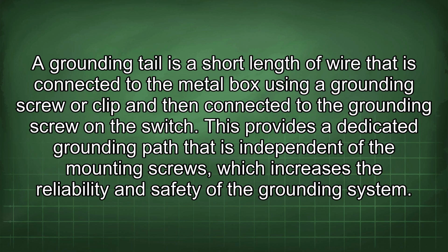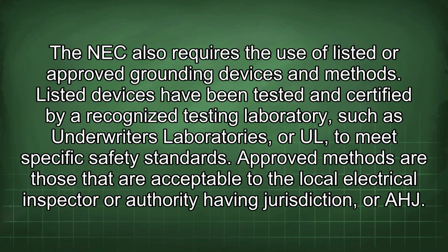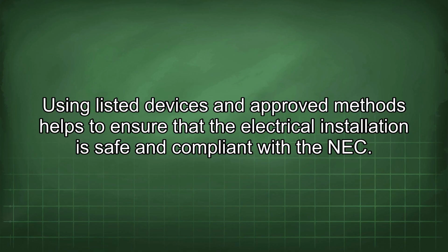The NEC also requires the use of listed or approved grounding devices and methods. Listed devices have been tested and certified by a recognized testing laboratory such as Underwriters Laboratories, or UL, to meet specific safety standards. Approved methods are those that are acceptable to the local electrical inspector or authority having jurisdiction, or AHJ. Using listed devices and approved methods helps to ensure that the electrical installation is safe and compliant with the NEC.